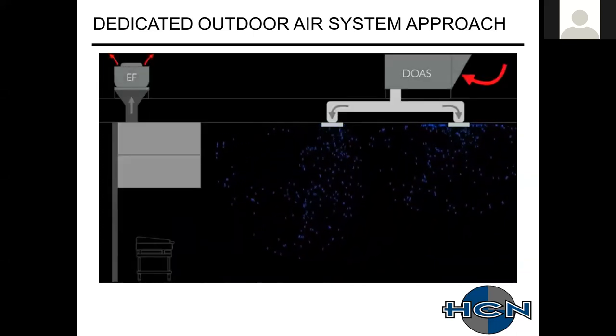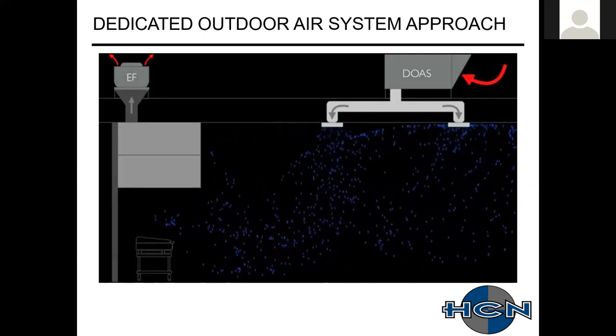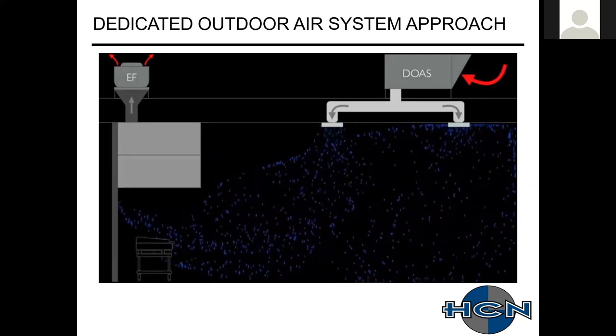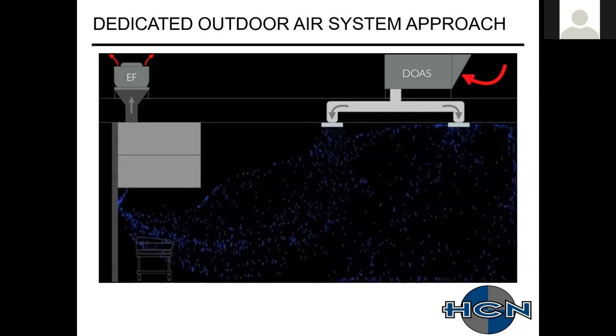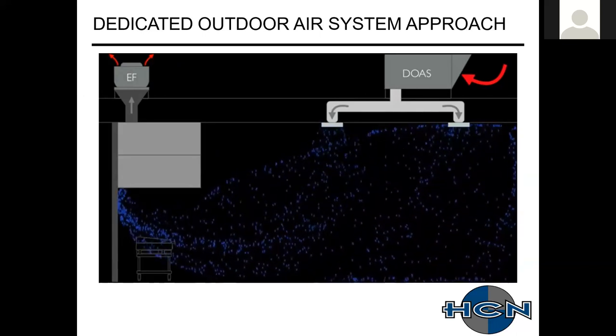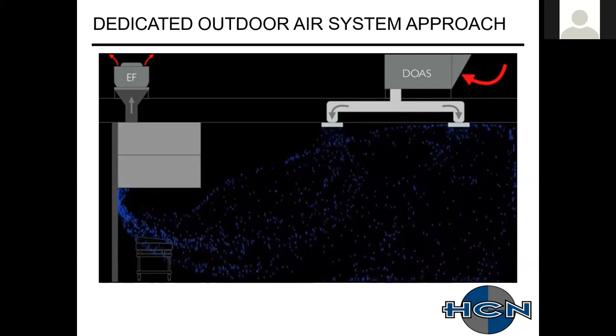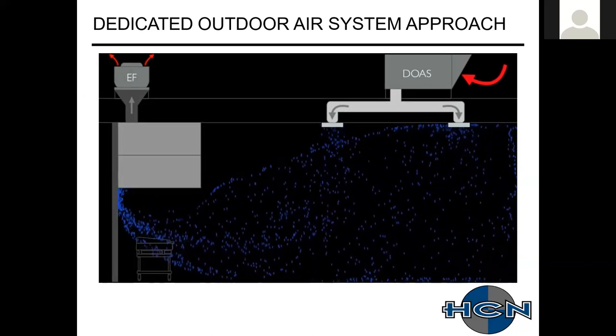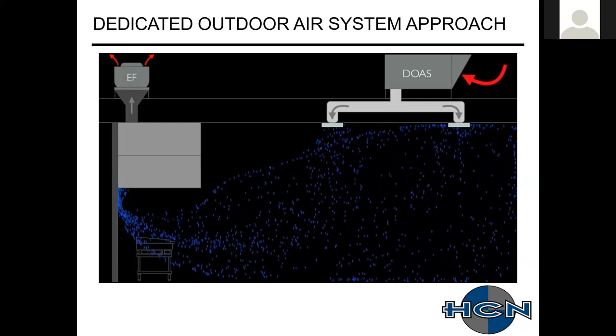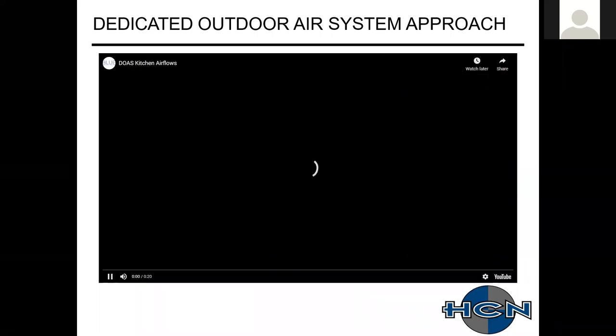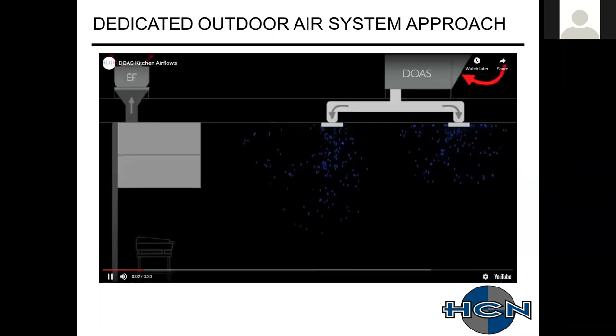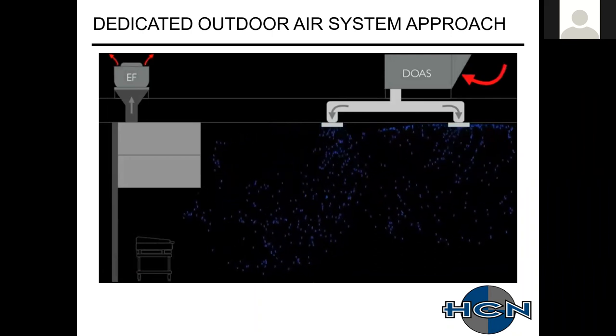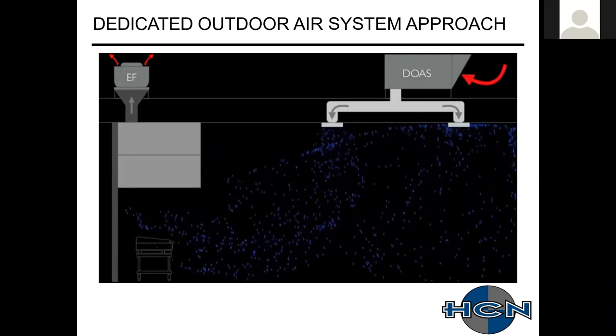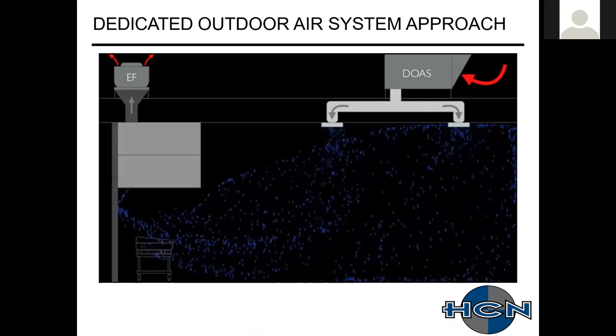So exhaust only hood, fresh air. It's filtered, nice, cool, comfortable air going right across your kitchen staff. They're sitting in front of that hot grill, and it feels really nice to them. Air just gets sucked right back up into the hood, and the system does what it needs to do. You have less fighting with the rooftop unit and makeup air unit. I've seen systems where your dedicated unit in the summertime is a heating unit, and the rooftop unit is in a cooling. If those aren't interlocked, you have one unit heating, one unit cooling.